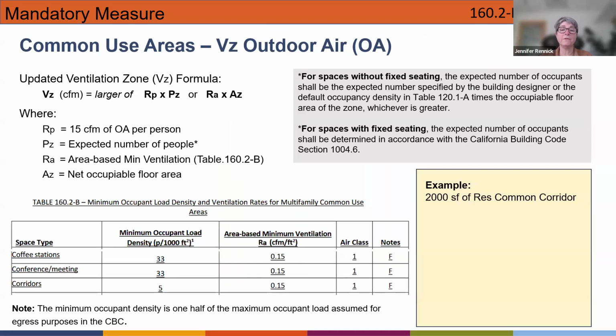For the common use area, the ventilation formula is different. A lot of times this is where, okay, you're going to be working with your mechanical engineer at this point anyway. So for anybody who's on the call that looks a little bit more on that side of things, I just want to give you a heads up that the formulas have been updated. I mean, when you look at the formula itself, it seems mostly the same, but what's changed is the table. So in essence, it changed the formula, even though mathematically it looks very similar. So there's a brand new table, 160.2-B, that has minimum occupant load density and the ventilation rates.